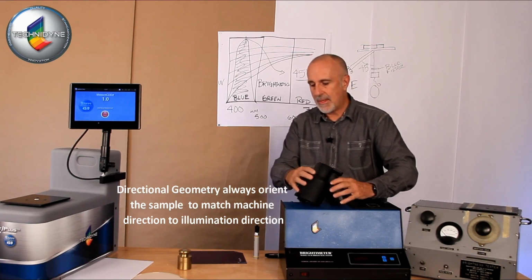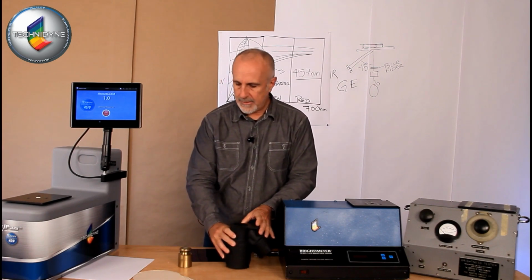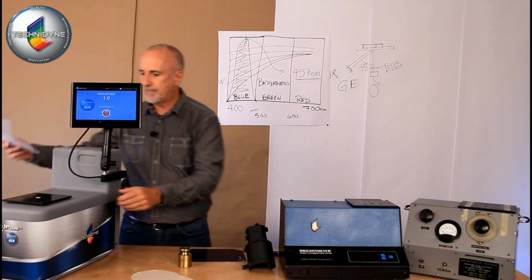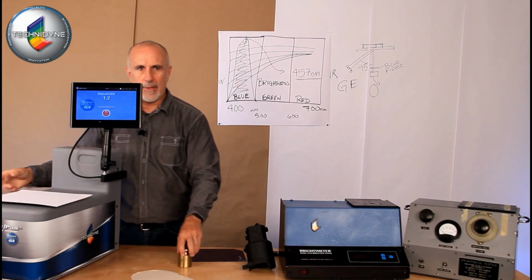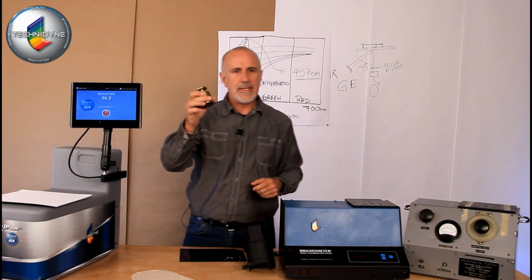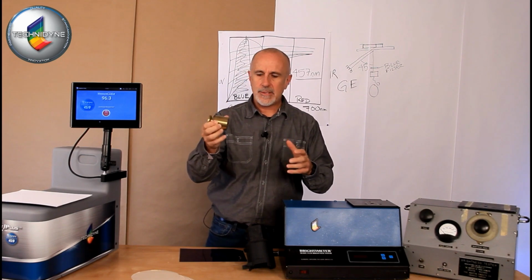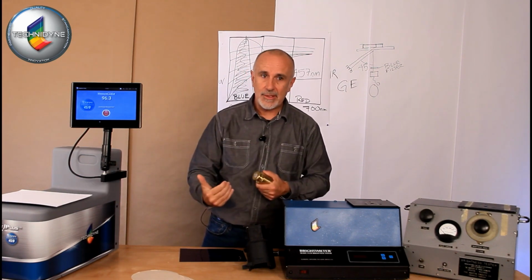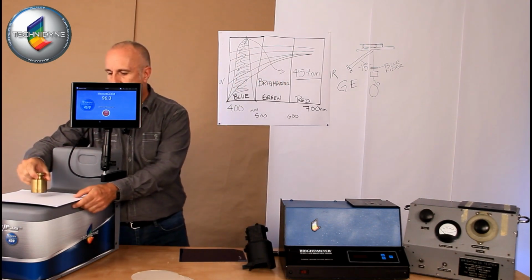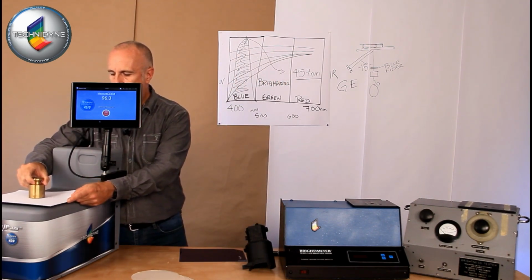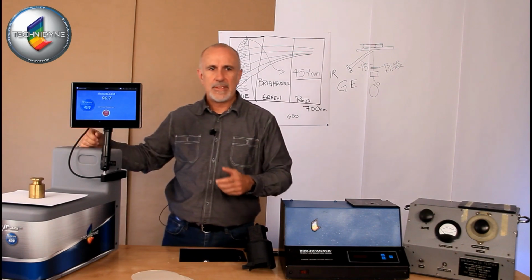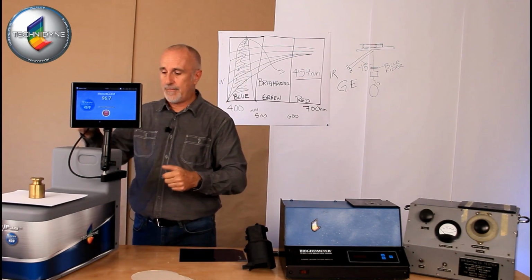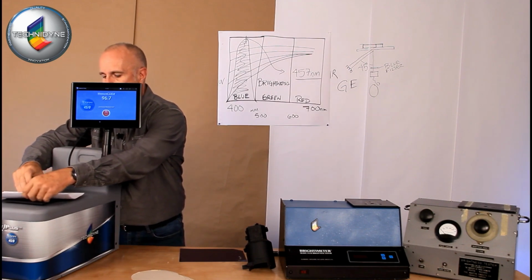And we can see that when we load a sample onto a TAPPI brightness instrument, and I load it this way, and it always comes with a 1 kilogram weight. And that's part of the standard because the backing is very important to the accuracy of the measurement. So you always want to use the 1 kilogram weight. You load the sample, you get the result, and the value is 96.7. Okay, I'm going to take this sample and I'm going to rotate it 90 degrees.